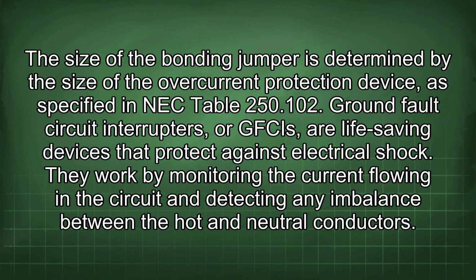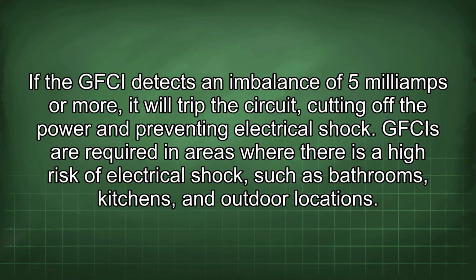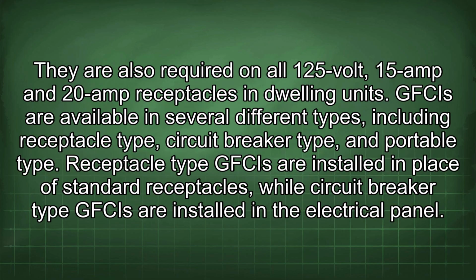They work by monitoring the current flowing in the circuit and detecting any imbalance between the hot and neutral conductors. If the GFCI detects an imbalance of 5 mA or more, it will trip the circuit, cutting off the power and preventing electrical shock. GFCIs are required in areas where there is a high risk of electrical shock, such as bathrooms, kitchens, and outdoor locations. They are also required on all 125-volt, 15 amp and 20 amp receptacles in dwelling units. GFCIs are available in several different types, including receptacle type, circuit breaker type, and portable type.